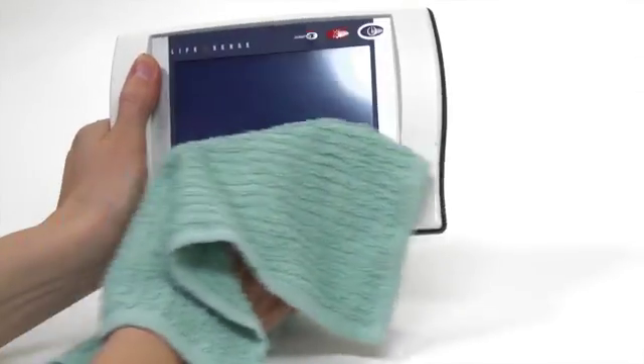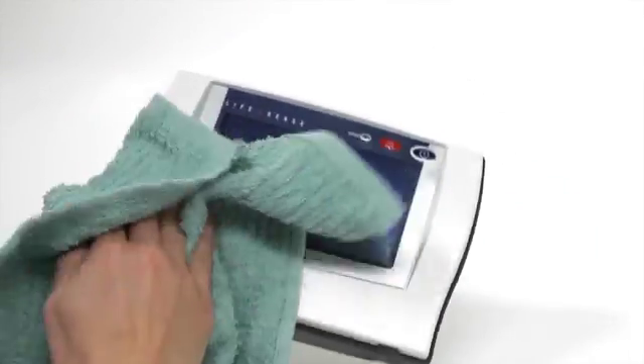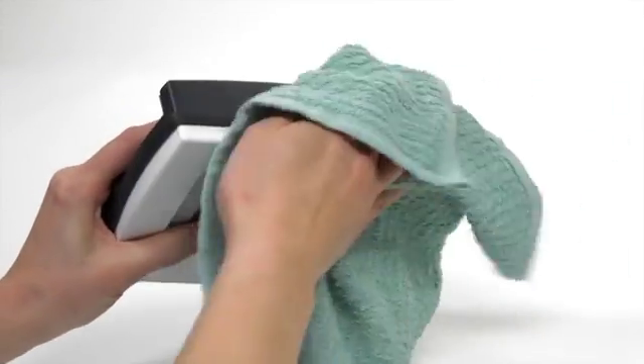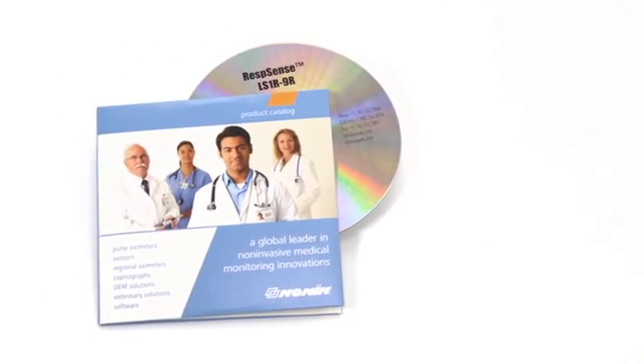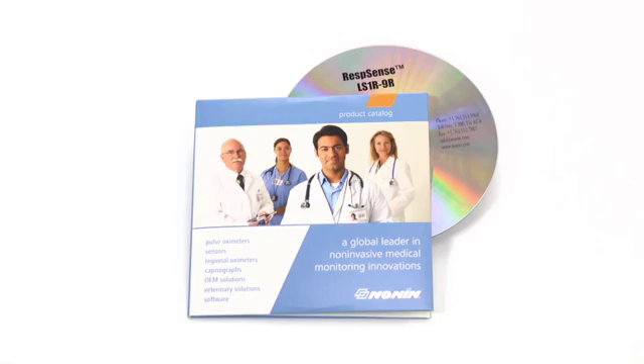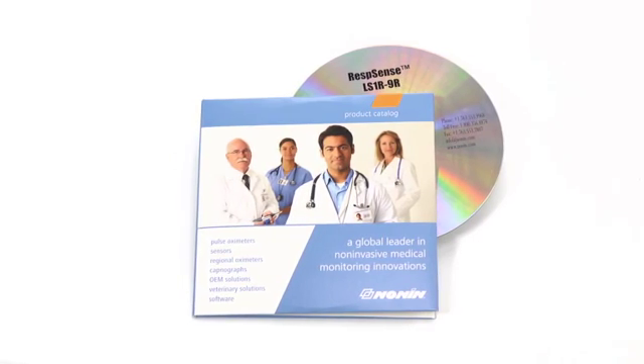Following use, you can clean the monitor with a soft cloth moistened with isopropyl alcohol. Allow the monitor to dry completely before use. Complete information for RespSense and LifeSense monitors can be found in the operator's manual provided with each product.